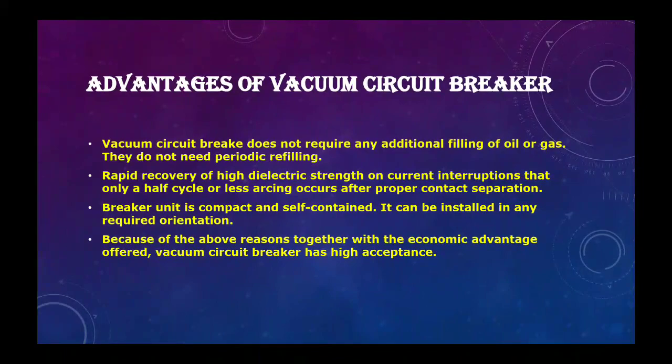Now, the advantages of a vacuum circuit breaker. Number one, it doesn't require any additional filling of oil or gas. They do not need periodic refilling also, because the contact material produces the vapor or the vacuum. Number two, the rapid recovery of high dielectric strength on current interruption, so that only half a cycle or less of arcing occurs after proper contact separation.